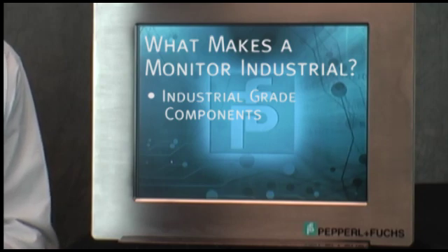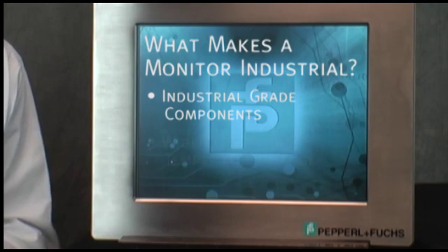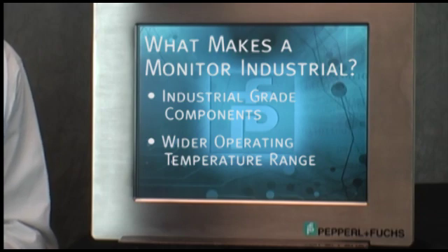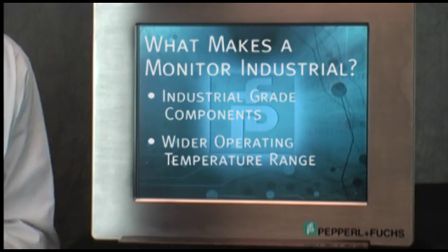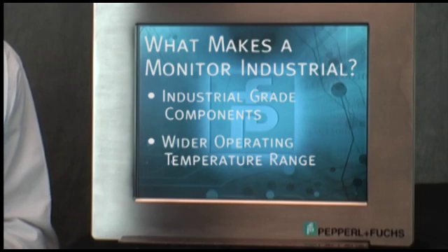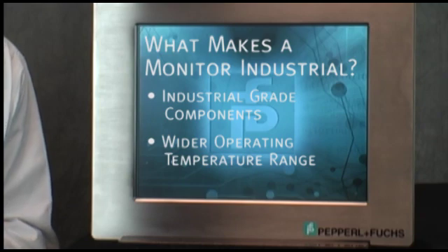Industrial is represented by a wider operating temperature range. Firstly, these monitors will start and run at a much colder temperature than a consumer grade monitor, all the way down through and in some cases below the freezing point. That has to do with the actual backlighting technology, and while it is fluorescent lamp technology, it will start and run at a lower temperature because they are industrial grade.